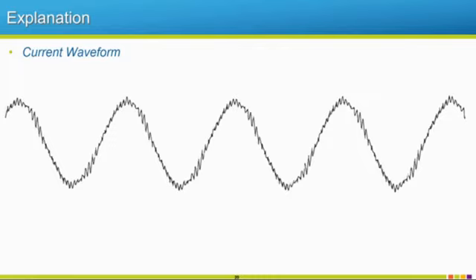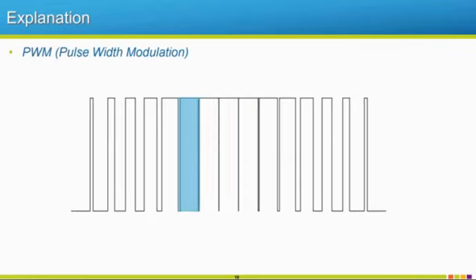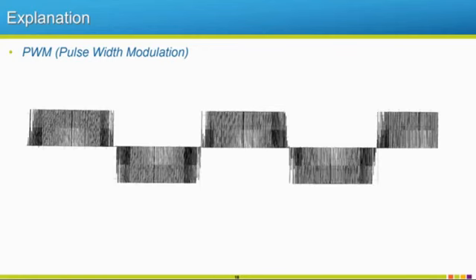Also with our voltage, I'm going to backtrack just a hair with our voltage waveform. This looks like a square wave, but really this is like the RMS voltage or average voltage of this cycle. And if you would look at it as the average voltage, this would look a lot more sinusoidal than it visually looks like from our oscilloscope reading. So it's still pretty sinusoidal, but you really see that difference with the current waveform. So just a little note there.